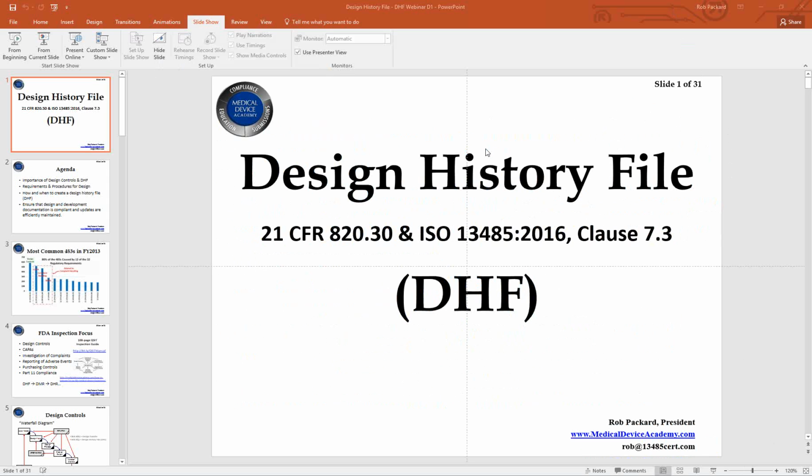But what I would include in there is, you want to be gathering each of your complaints through the post-market surveillance process, as well as non-complaints like literature data, MAUDE database for competitor products, different things like that. And you're also going to be reviewing service data, and you're going to have that as an input into the design process to assess whether you need to make corrections to the design or improvements to the design. So that's one of the ways that you're going to include it.